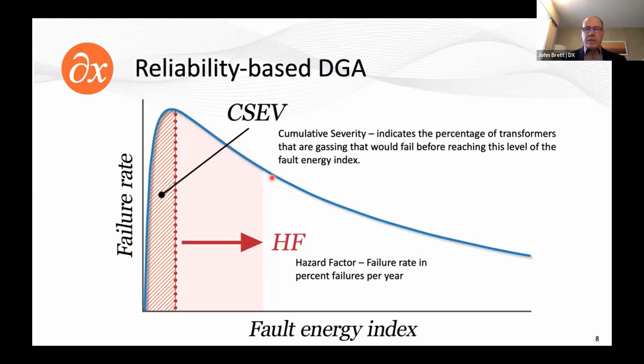Now we've done a lot of work on this in the context of looking at all the key gases, the hydrocarbon gases, all of them, and the carbon oxide gases as well. A number of customers have also been asking us, what about hydrogen only? Can we do this for just hydrogen or composite gas monitors? Today I'm going to use hydrogen, but just know that it applies fairly generally for single gas or composite gas. And yes, a similar curve does exist for hydrogen.